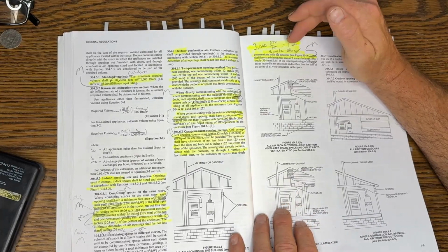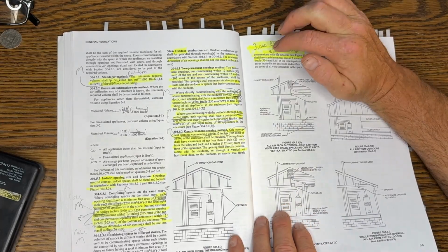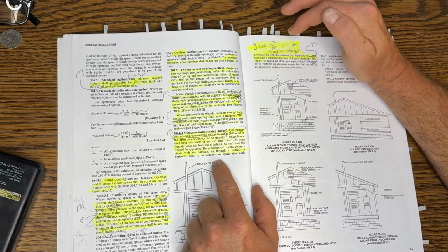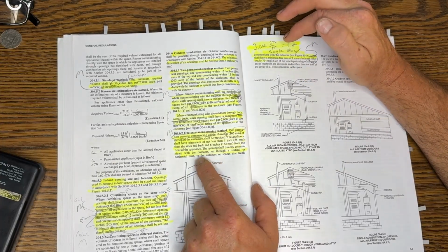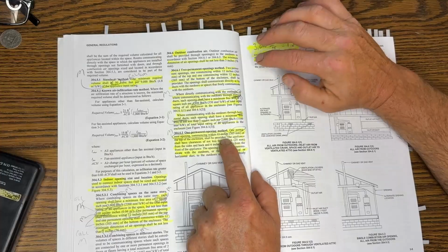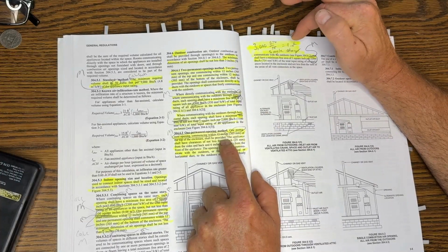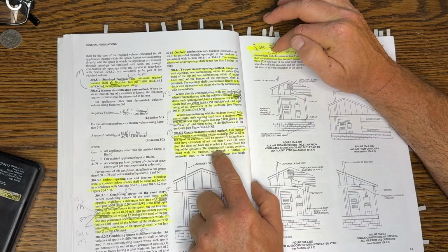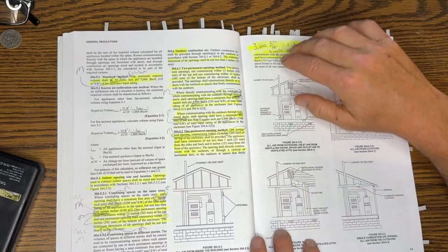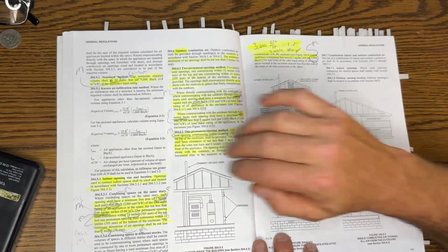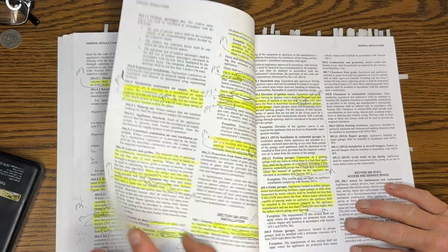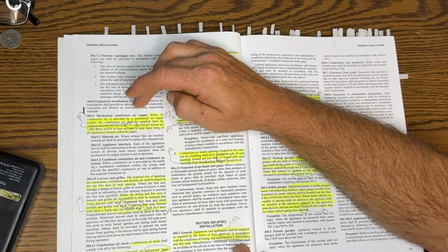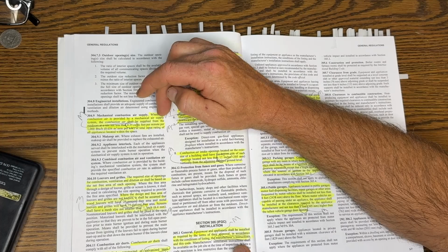Let's see, I'm trying to think. Just bear with me. Single opening. One permanent opening method. There you go. If you have the one permanent opening method instead of the two permanent opening method, it's 1 square inch per 3,000 BTU, and they have some parameters here in terms of what you need to do. So anyway, just know this section. There's a lot of questions that came up from that section, and forgive me for flubbing through it. It's been a little while since I looked at it. Mechanical combustion air supply.